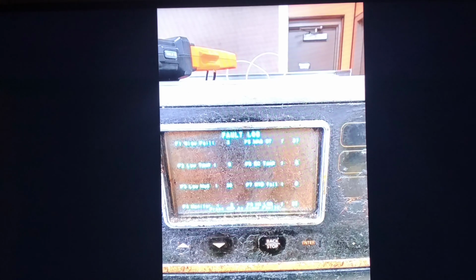F3, low mag error, you got 20 of those. F5, mag over temp, meaning the magnetron's overheating, you got 37 of those. And then down below you have F8, which is heat exchange low, HX low, and they have about 30 of those.